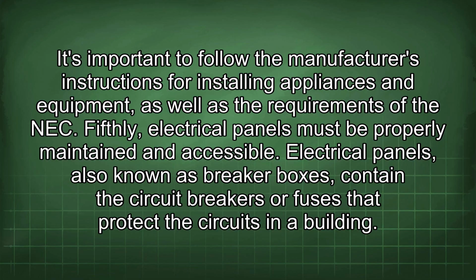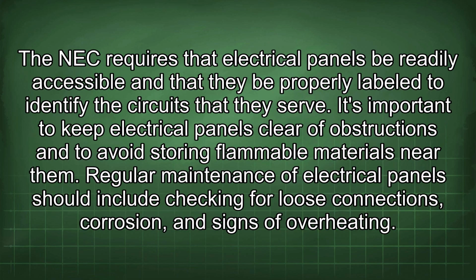Fifthly, electrical panels must be properly maintained and accessible. Electrical panels, also known as breaker boxes, contain the circuit breakers or fuses that protect the circuits in a building. The NEC requires that electrical panels be readily accessible and that they be properly labeled to identify the circuits that they serve. It's important to keep electrical panels clear of obstructions and to avoid storing flammable materials near them. Regular maintenance of electrical panels should include checking for loose connections, corrosion, and signs of overheating.